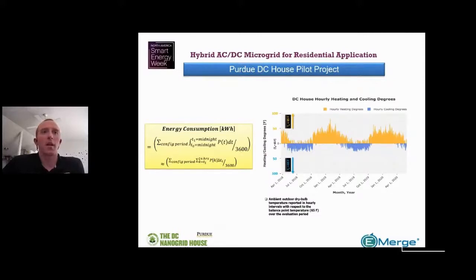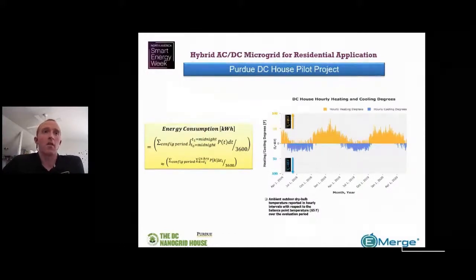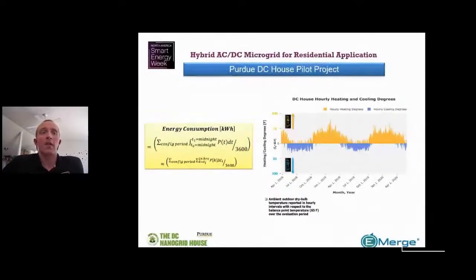We've measured the energy consumption, particularly from the heat pump for heating and cooling that space, compared to the weather conditions outside. That allows us to determine a system effectiveness—so if it's 20 degrees Fahrenheit outside and we want the house to be at this 65-degree Fahrenheit balance point, how effectively is the heat pump heating in that specific circumstance?